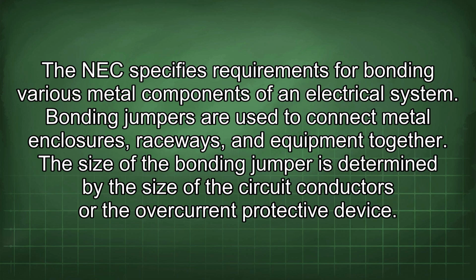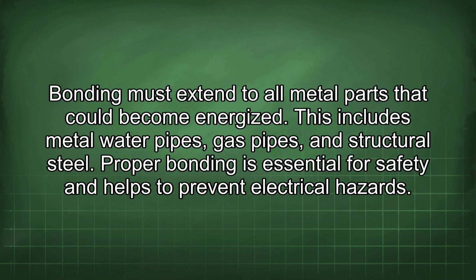Bonding jumpers are used to connect metal enclosures, raceways, and equipment together. The size of the bonding jumper is determined by the size of the circuit conductors or the overcurrent protective device. Bonding must extend to all metal parts that could become energized. This includes metal water pipes, gas pipes, and structural steel. Proper bonding is essential for safety and helps to prevent electrical hazards.